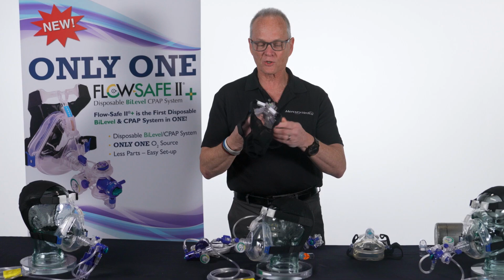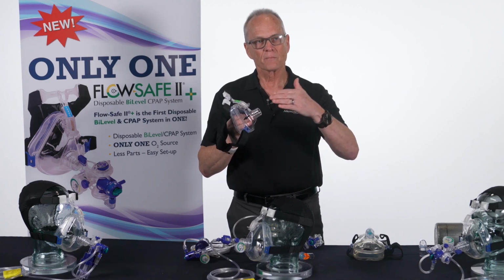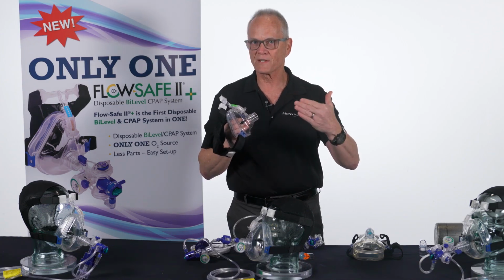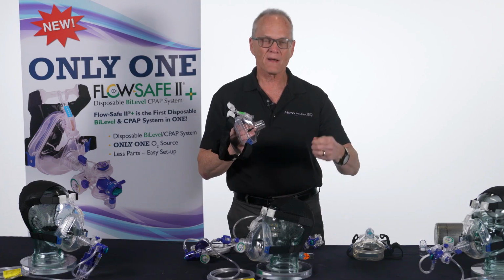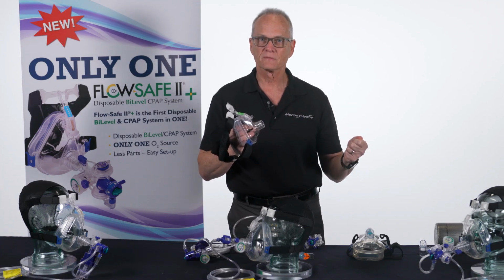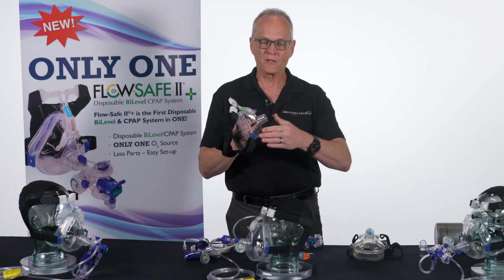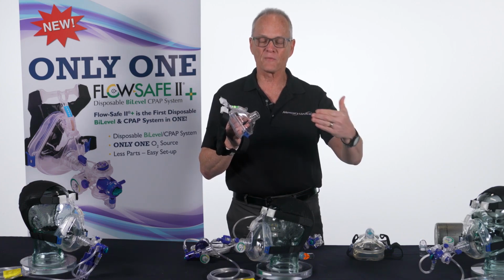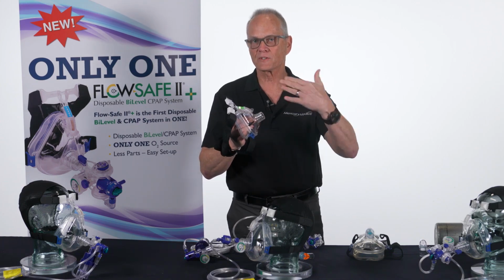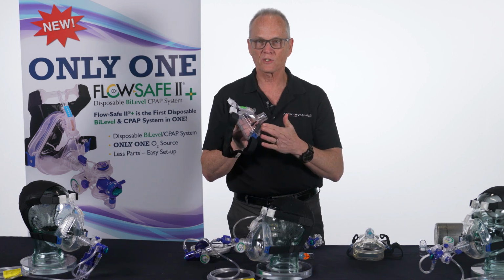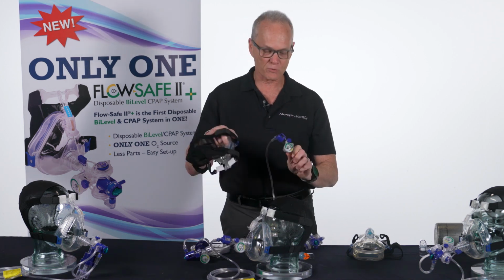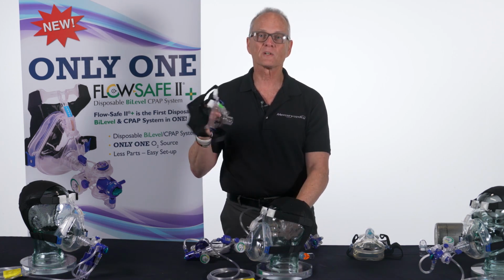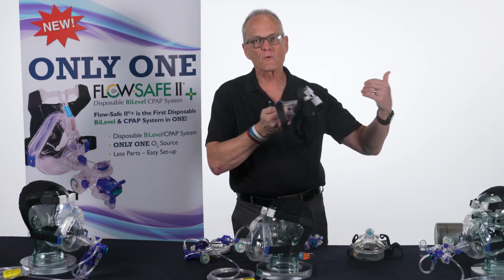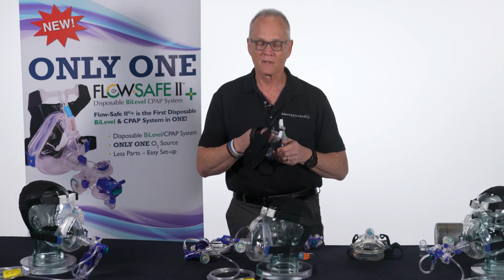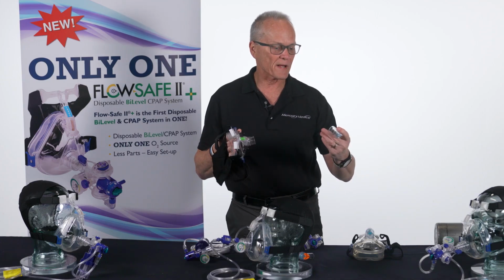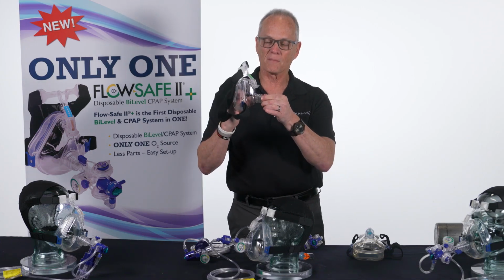So there is a way to turn this into a very close version of a vented mask. You need two things. You have to have an anti-asphyxia valve, which this does not have, and you've got to have a valve that is able to flush the CO2 out of the mask, which this does not have. Because remember, I told you this was an open system, so it doesn't need any of those things. But the other devices the hospital uses do. So we have a different valve that can actually be placed into the mask.